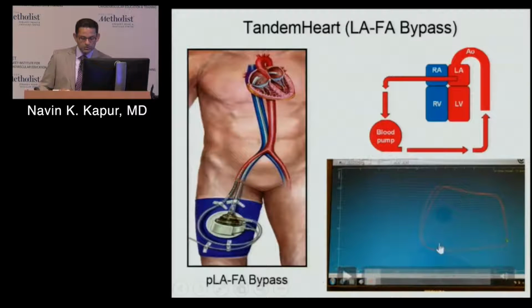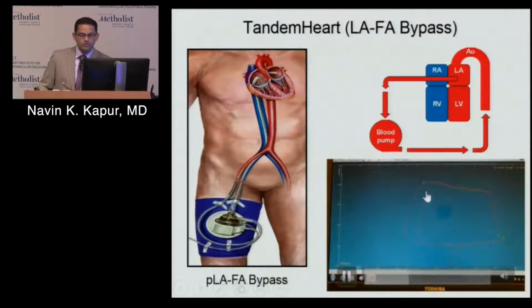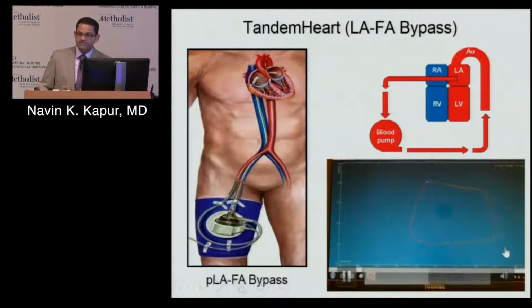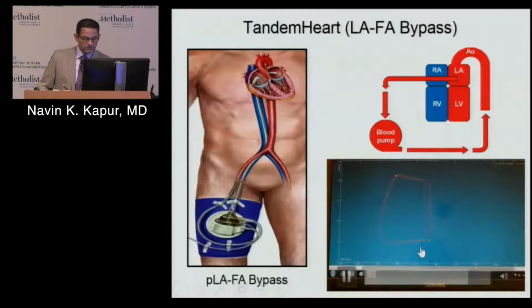This is the normal pressure-volume loop before we activate a Tandem device. Here we activate the Tandem device, and the green dots are volume and the blue dots are pressure. Once we activate the Tandem device in that LAFA configuration, all of a sudden you see a significant drop in volume, but you don't see much of a drop in pressure. Remember, our goal is to drop pressure and volume. In this case, we've gotten rid of volume, but we haven't gotten rid of pressure.